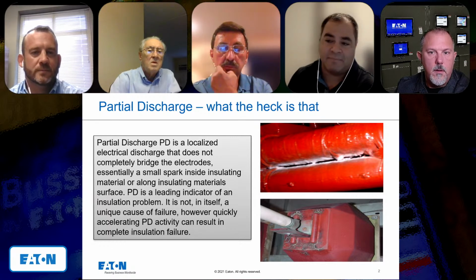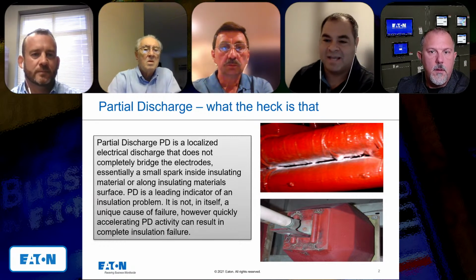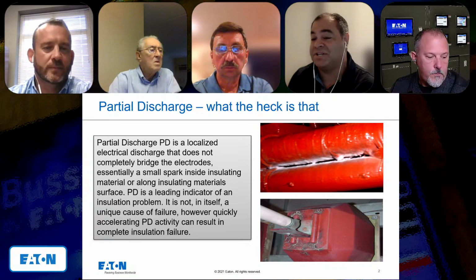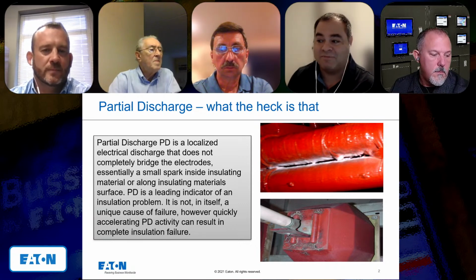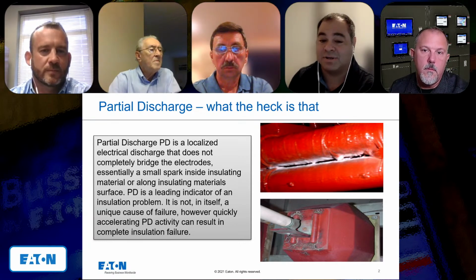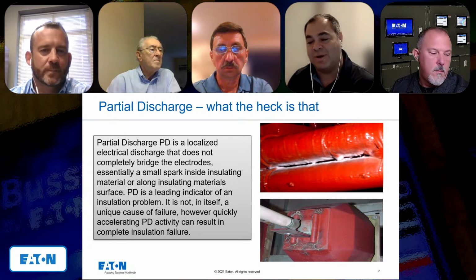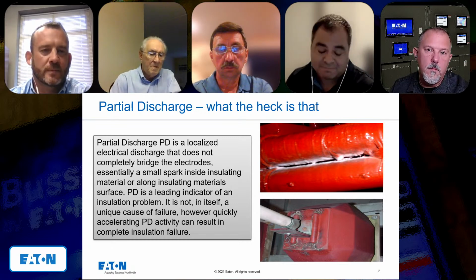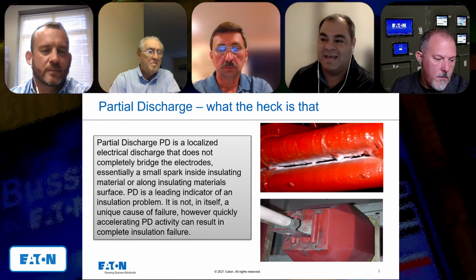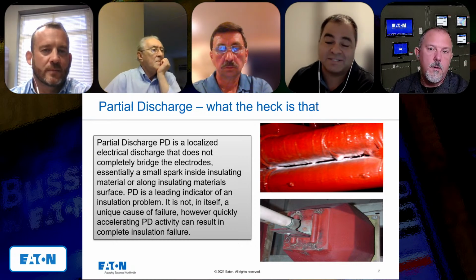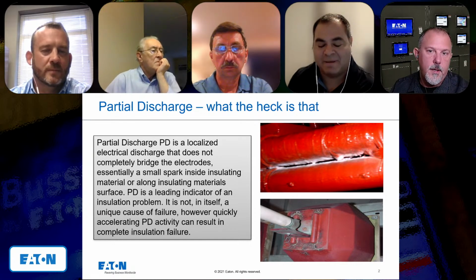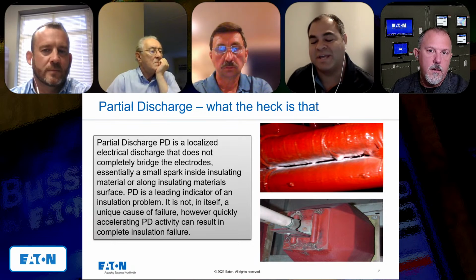For example, if you have a bus duct and suddenly you have partial discharge there, probably it's coming from humidity getting inside the bus duct. In those cases, you need to act faster because it could end in a failure within a few weeks or months. So everything depends on the asset you're looking at.